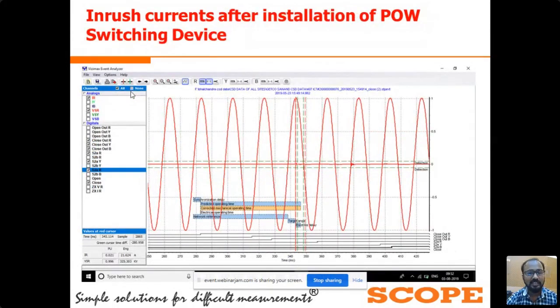So now we will see the waveform with the control switching device. Here you can see the waveform we have recorded for the same CSD with the control switching operation. This continuous waveform is the system voltage waveform, and at this cursor position we have targeted this point. Here we can see a normal spike here and here. Only a normal spike is there. This is the no load current of the power transformer that we have observed during the charging.